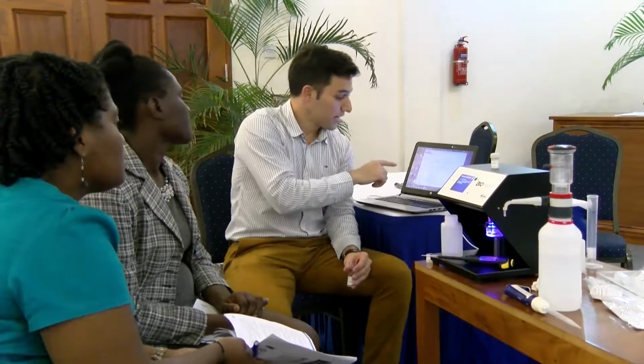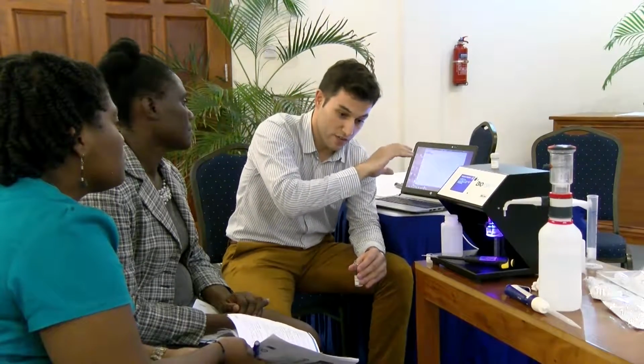Okay, we can proceed to the calibration process. What we are going to see now is how the current reaches a stable stage, and once the intensity is stable, the device asks us to add 2 milliliters of calibration standard. We add 2 milliliters, and in that moment this liquid has a concentration of histamine. The enzyme will detect this concentration, and you'll see a change in the current, a jump, as a consequence of the histamine addition. When a second stable stage has been reached, the device will ask for a second addition.